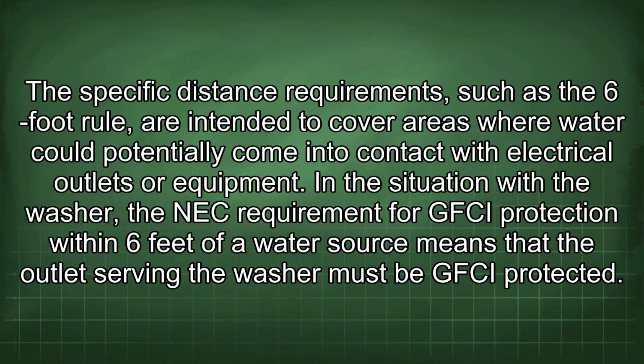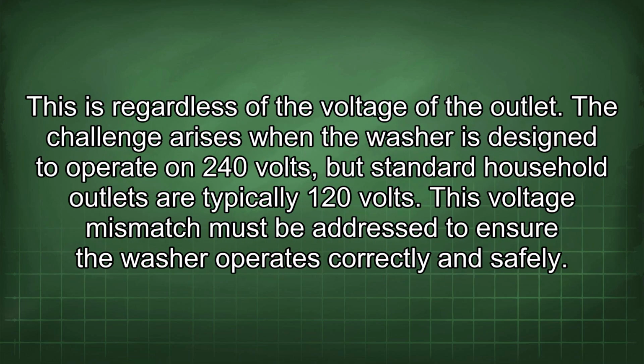In the situation with a washer, the NEC requirement for GFCI protection within 6 feet of a water source means that the outlet serving the washer must be GFCI protected. This is regardless of the voltage of the outlet. The challenge arises when the washer is designed to operate on 240 volts, but standard household outlets are typically 120 volts. This voltage mismatch must be addressed to ensure the washer operates correctly and safely.